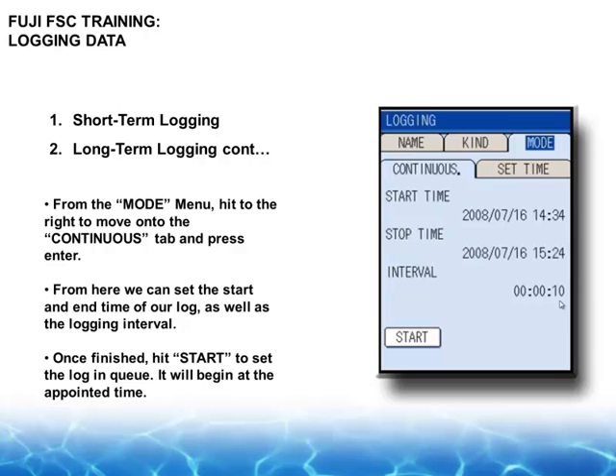And the bottom here is the interval. It's adjustable from 10 seconds and on up. The only caution I have is, depending upon your application, if you're looking for toilet flushes, then you go down to the 10-second intervals. If you're looking for traditional process control monitoring, in that case, most people tend to sample once a minute. With that in mind, you get 1,440 data points in a day. So that's flow rate, and then times what other item you've checked off as well. So that's a massive amount of data.